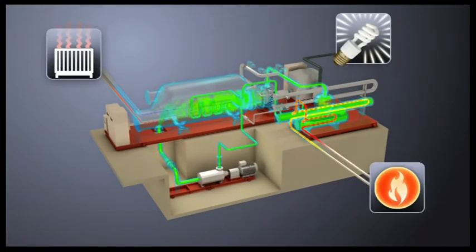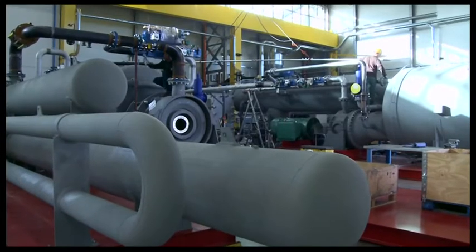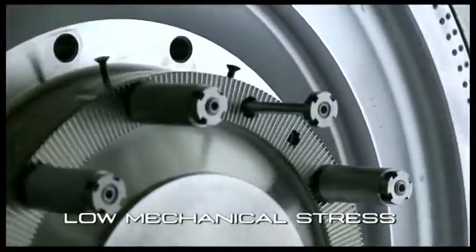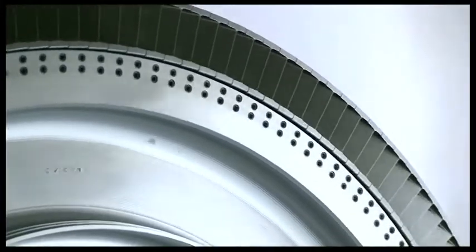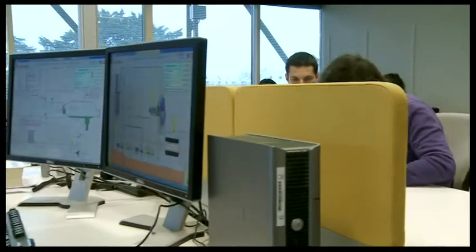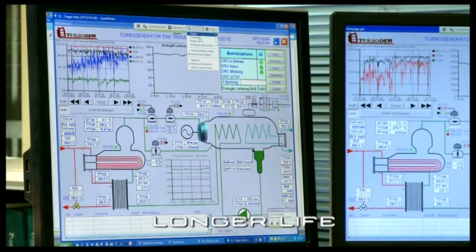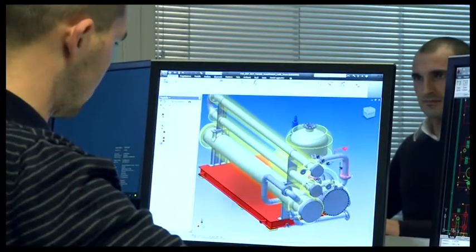Aside from high cycle efficiency, the ORC system has many other significant advantages. Low mechanical stress of the turbine due to low peripheral speed. Low turbine RPM allows the direct drive of the electric generator without a speed reduction unit. The absence of vapor humidity guarantees a longer life for the turbine and independent functioning with no on-site operator required.